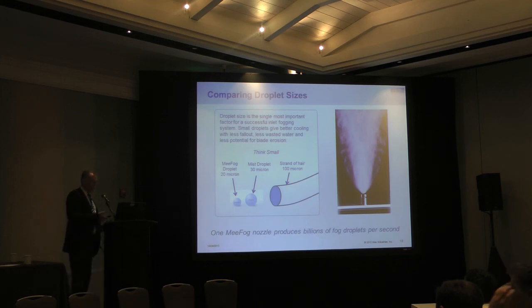Comparing droplet sizes is probably the single most important factor in evaporative cooling with fogging, or overspray with fogging: droplet size. So smaller droplet size means it evaporates faster, it produces more cooling more quickly, you use less water because you have less fallout. There are many, many advantages to it. This just shows an example of how small a fog droplet can be. That's a 20 micron droplet and a 100 micron strand of human hair. Each nozzle is actually producing billions of droplets per second.